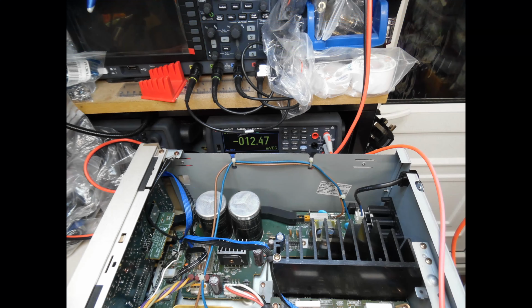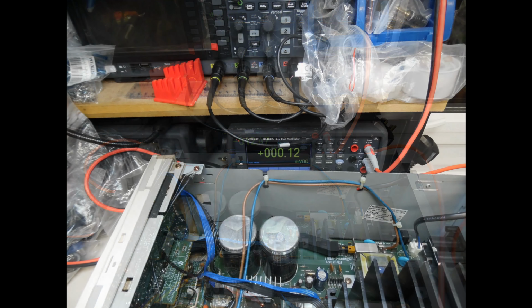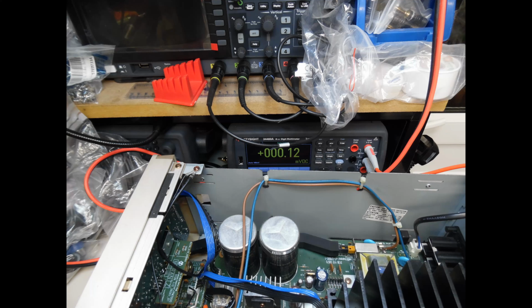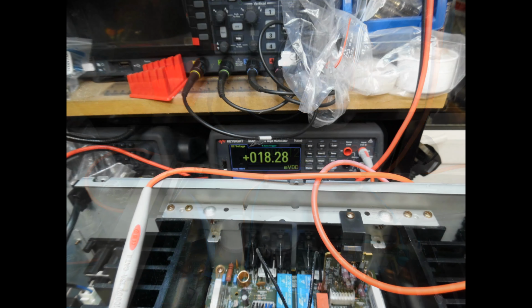So here you can see that we're measuring on the rear terminals. You can just make out the multimeter leads. And we have a reading of 12.47 millivolts, so it's a little bit high. And then once we've made the adjustment, you can see here we're way down now to 0.12 millivolts, which is great, well within the tolerance. And then here you can see we have the AB mode. We've got this roughly to about 18.28 millivolts, which is perfect.